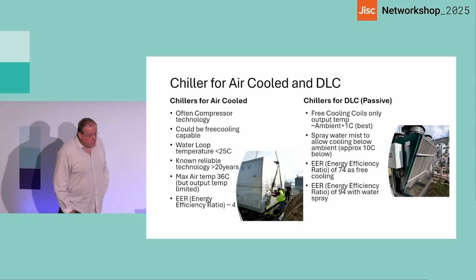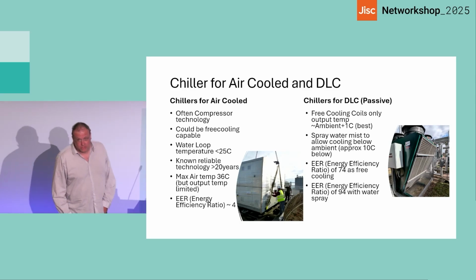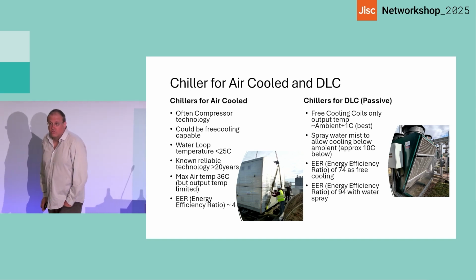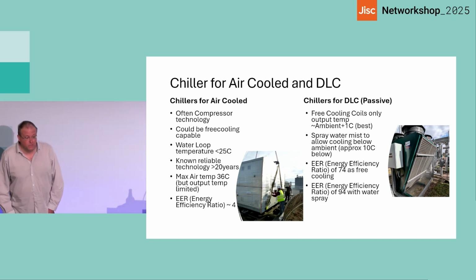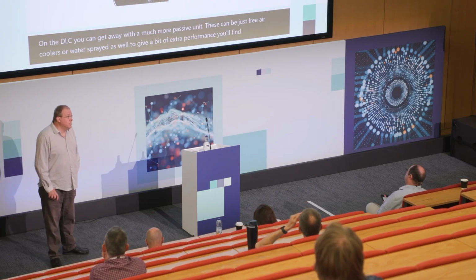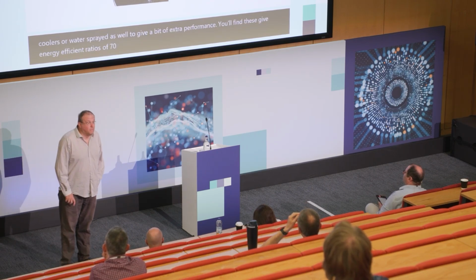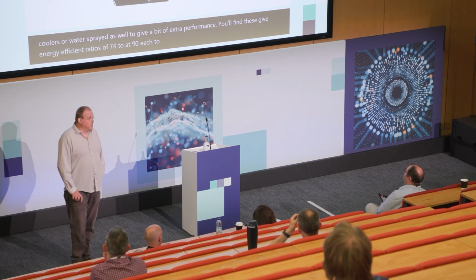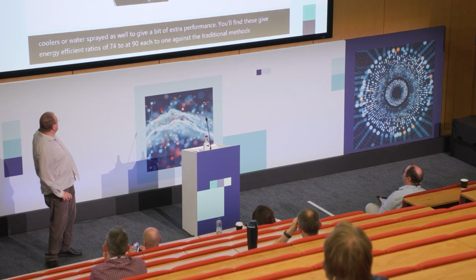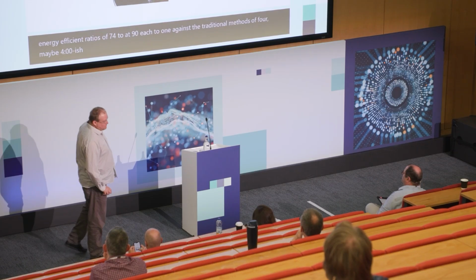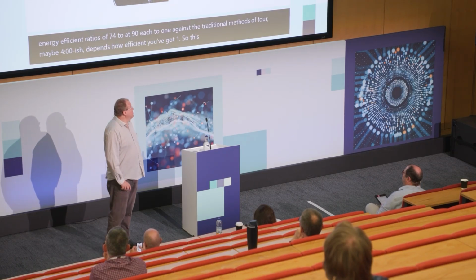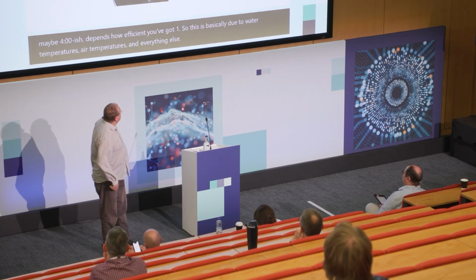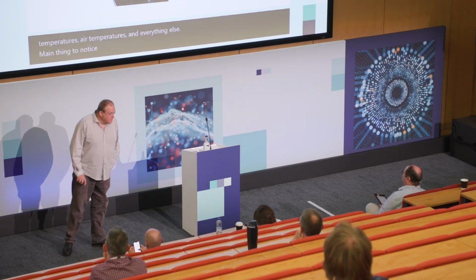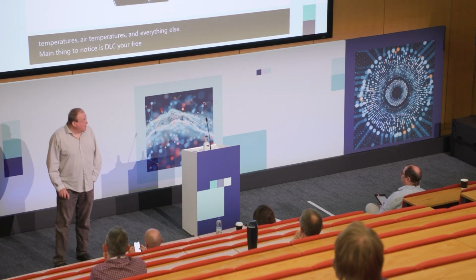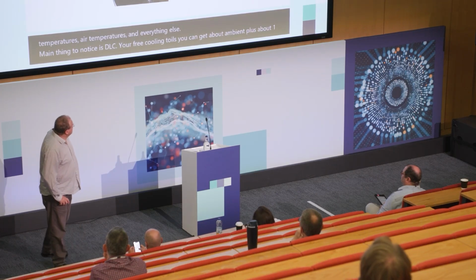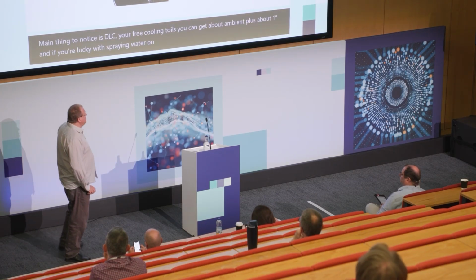On the DLC, you can get away with a much more passive unit. These can be just free air coolers or water sprayed as well to give a bit of extra performance. You'll find these give energy efficiency ratios of 74 to 90 each to 1, against the traditional methods of 4, maybe 4-ish. Depends how efficient you've got one. So this is basically due to water temperatures, air temperatures, and everything else. Main thing to notice is DLC, your free cooling coils, you can get about ambient plus about 1 degree. And if you're lucky with spraying water on it, you'll get about 10 degrees below ambient.